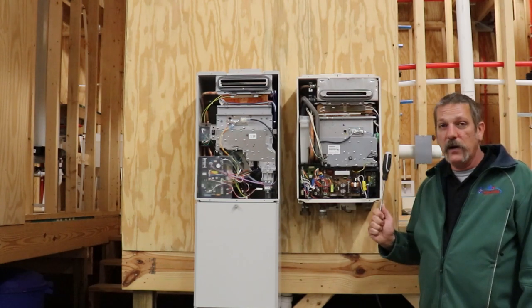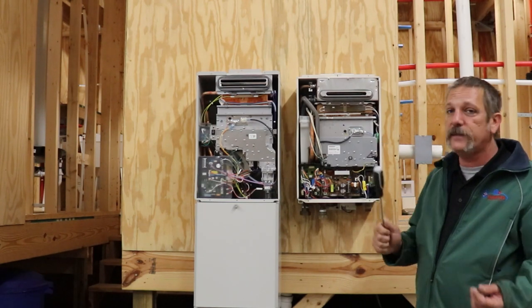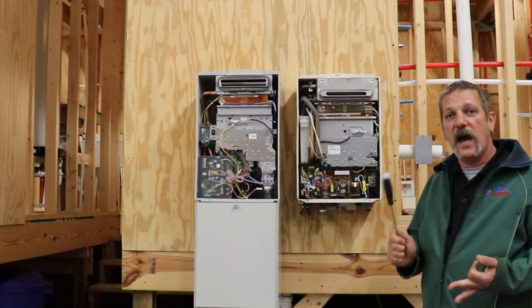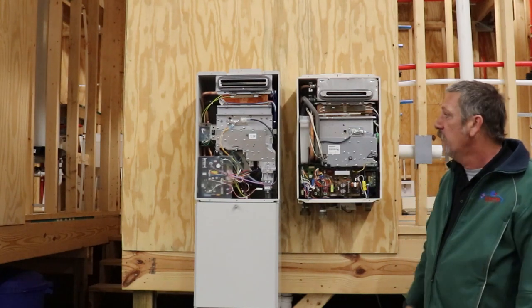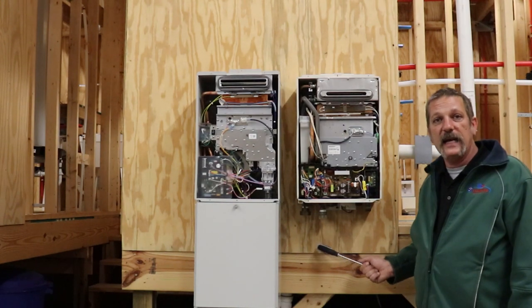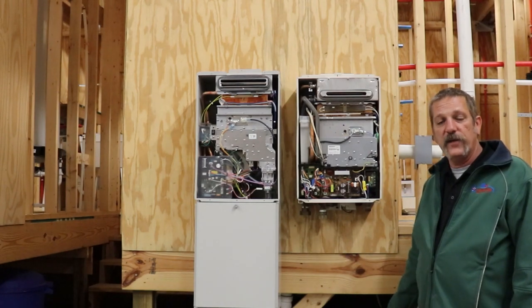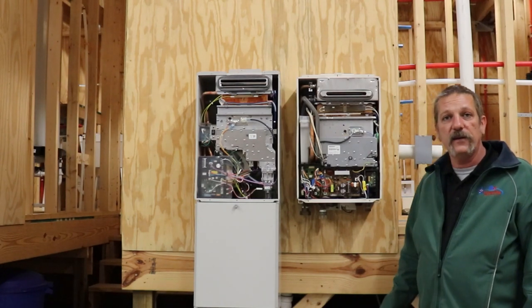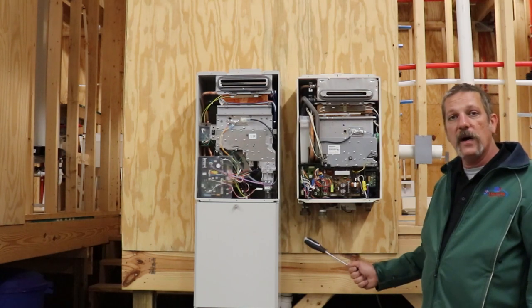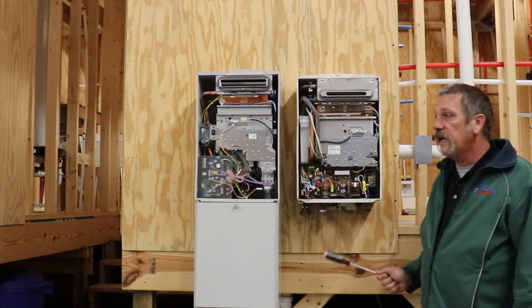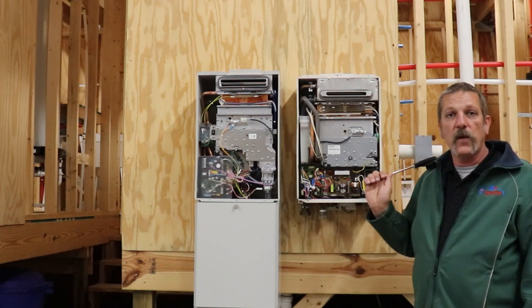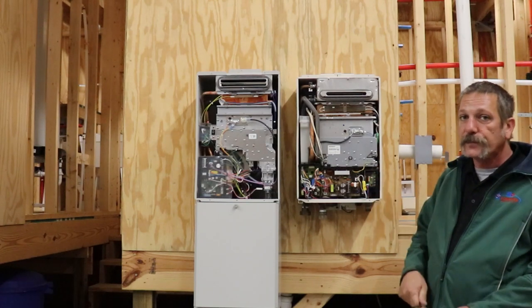Now, if you have an interior one, which I highly recommend because it keeps it out of the bugs and the sunshine and the weather and elements and all that, you do have to run a dedicated condensate line for this one. You can't tie it into the relief because if that relief were ever to open up, it's gonna blow back up that condensate line, fill that box up, and flood your water heater out. You don't want that to happen.